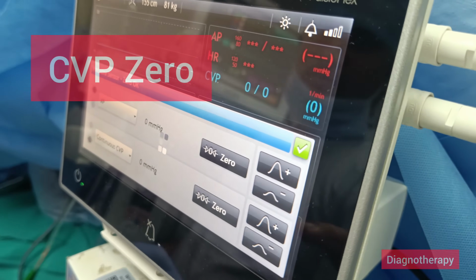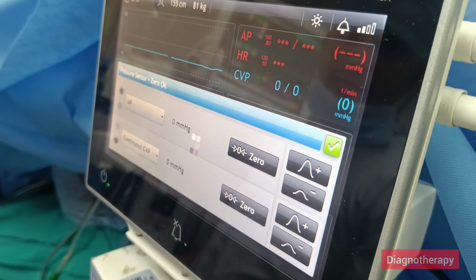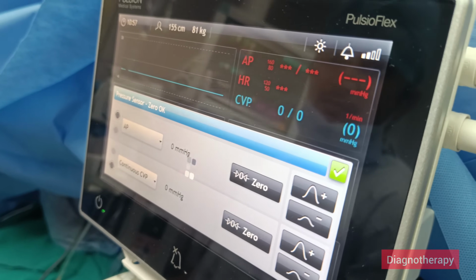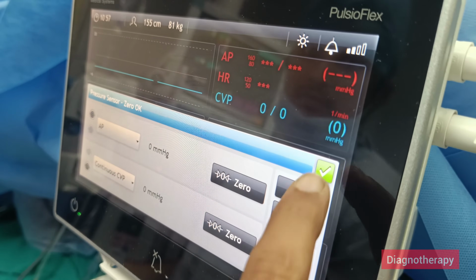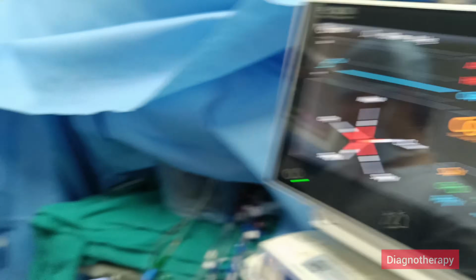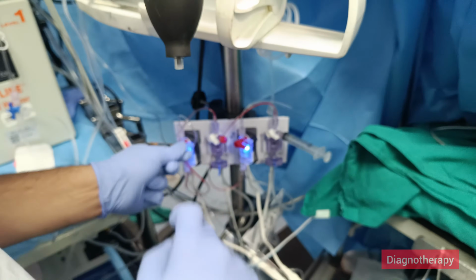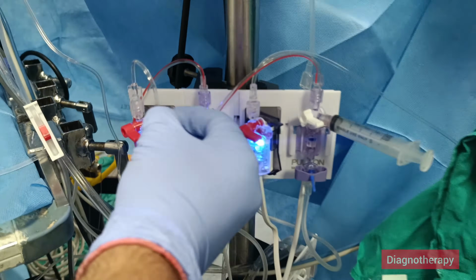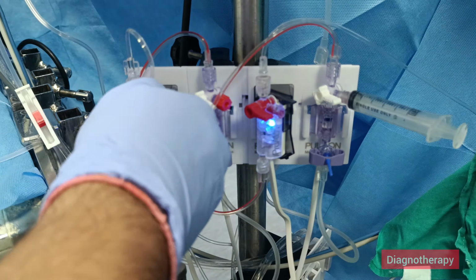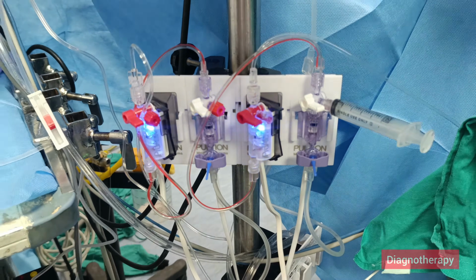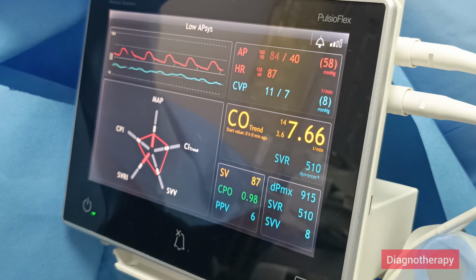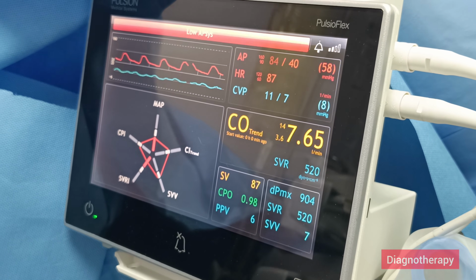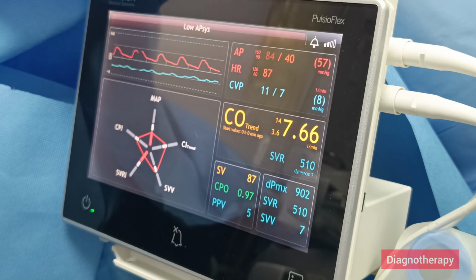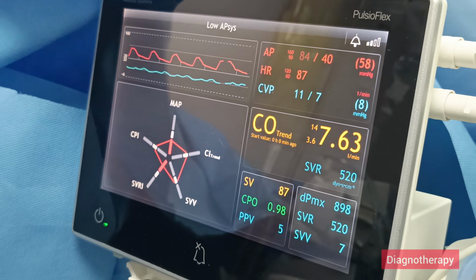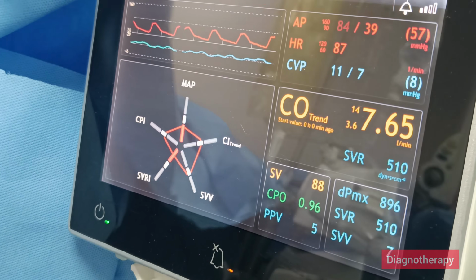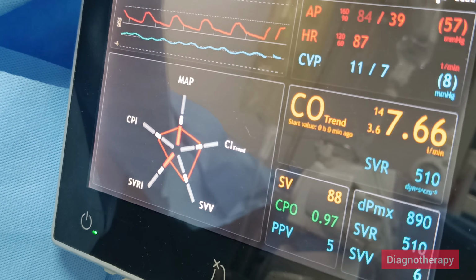For CVP also, we need to do the zeroing. So after touching, there will be a timer. Now it is done. Press the tick mark and close the three-ways. Three-way cocks will be closed. After that, we can see both the waves on the screen. You can see arterial pressure and CVP. The waves are being displayed on the cardiac output monitor.